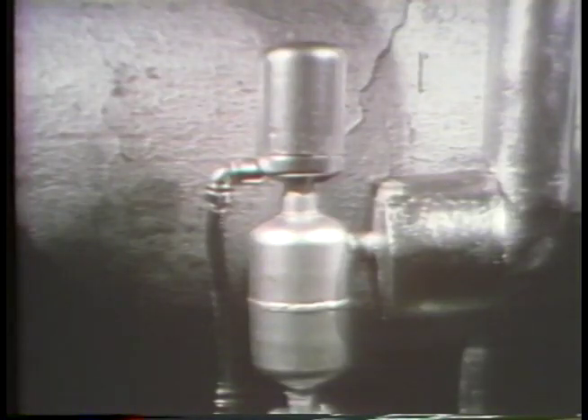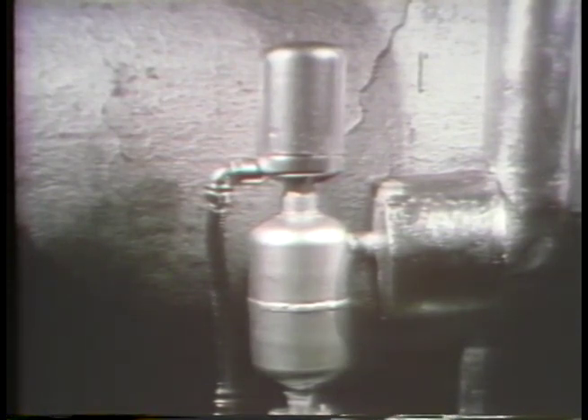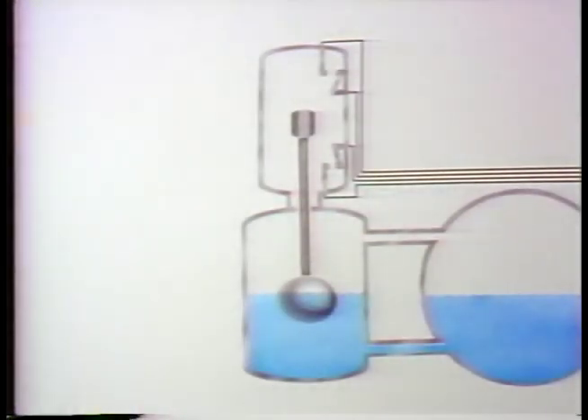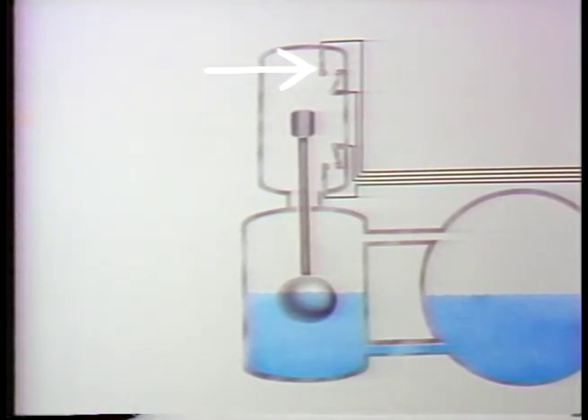Float devices can also be used to initiate alarms, usually by opening or closing contacts on an electrical switch. This is a typical float instrument that uses a magnetic switch to initiate level alarms on a feedwater heater. In this drawing, you see the float and the contacts for the magnetic switch. This is the switch for the high-level alarm, and this is the one for the low-level alarm.